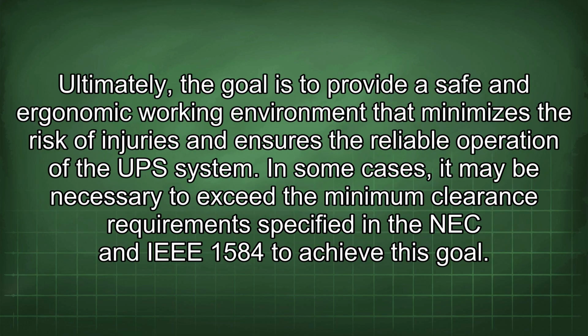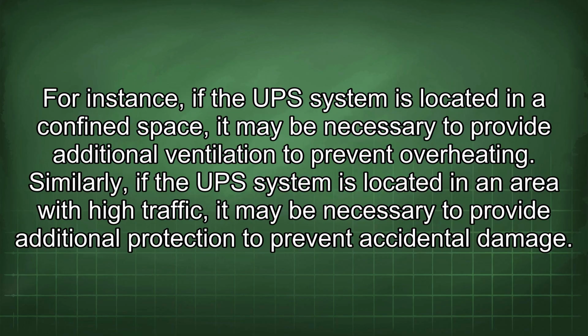Ultimately, the goal is to provide a safe and ergonomic working environment that minimizes the risk of injuries and ensures the reliable operation of the UPS system. In some cases, it may be necessary to exceed the minimum clearance requirements specified in the NEC and IEEE 1584 to achieve this goal. For instance, if the UPS system is located in a confined space, it may be necessary to provide additional ventilation to prevent overheating. Similarly, if the UPS system is located in an area with high traffic, it may be necessary to provide additional protection to prevent accidental damage.